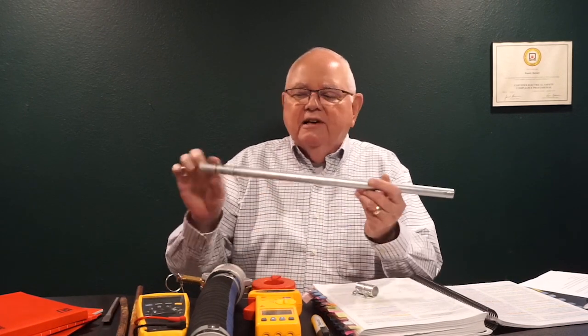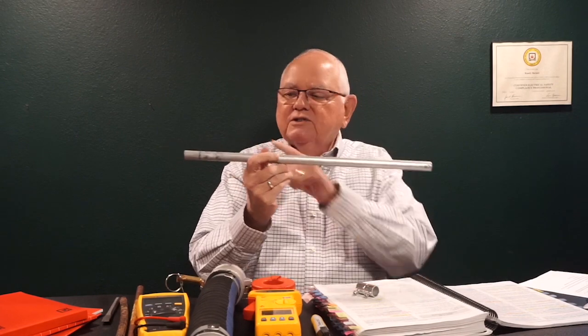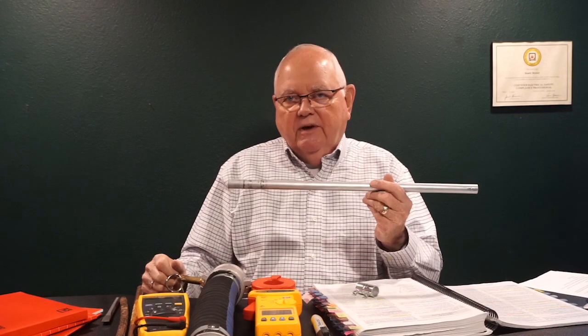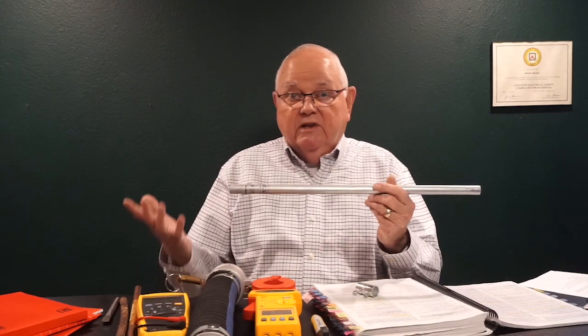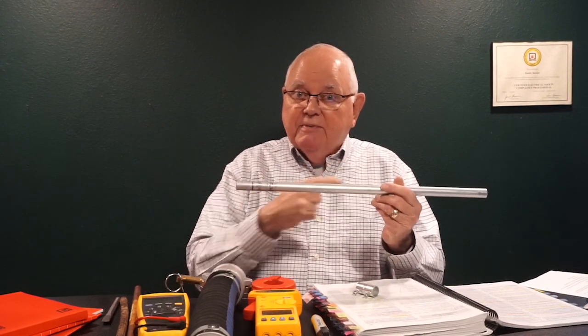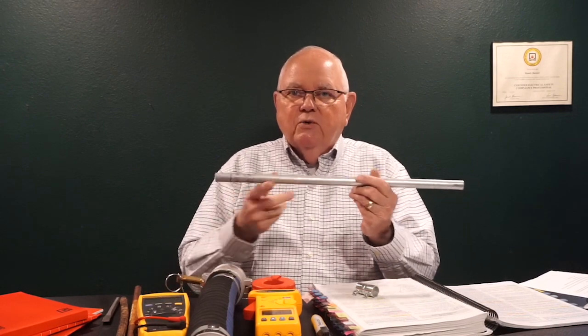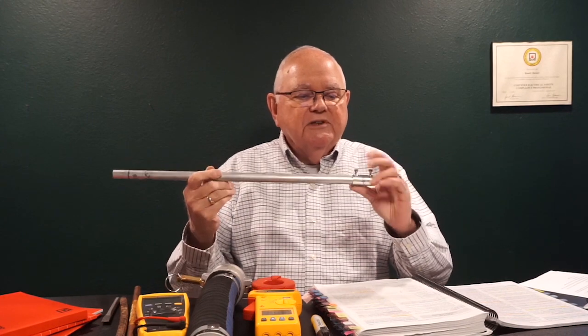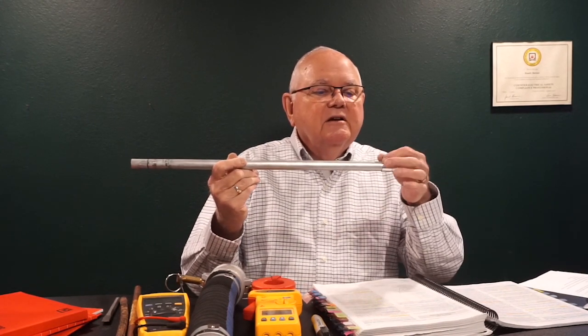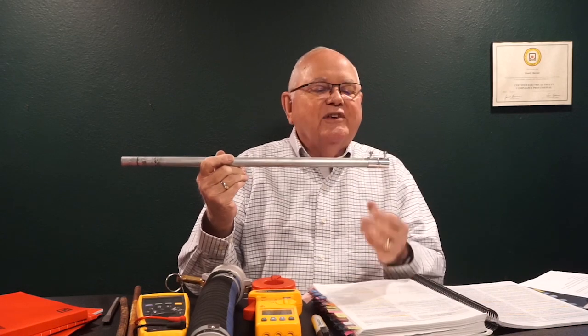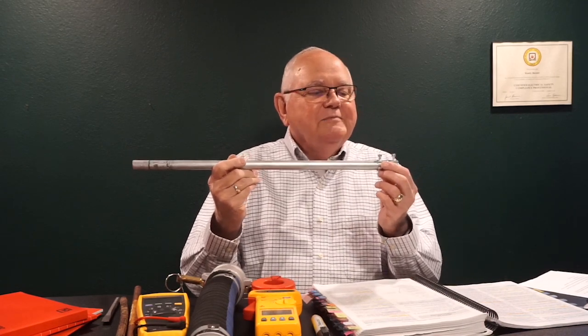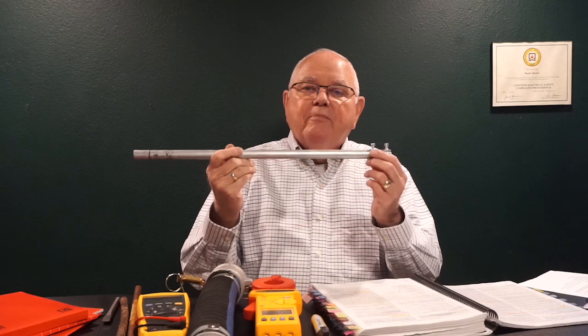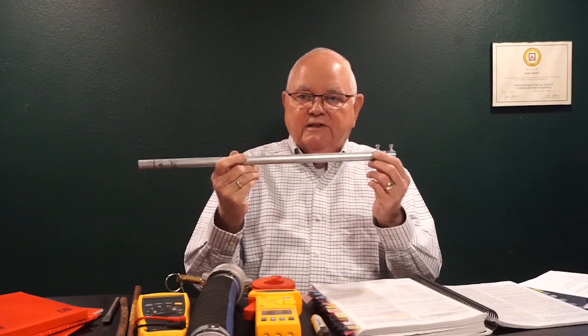If I take, here's for instance, a piece of conduit. If for some reason current flows into this piece of conduit, where does it want to go? It wants to go back to the source. I've had a ground fault down here in a piece of equipment. Current wants to get back to the source. Let it go there. Give it a good low impedance path all the way back to the source. So when I join this piece of conduit to another piece of conduit, I want to make sure that I get a good tight fitting. So I'm going to take my screwdriver, obviously, and tighten that down. And so I want proper bonding to carry all my fault current back to the source.